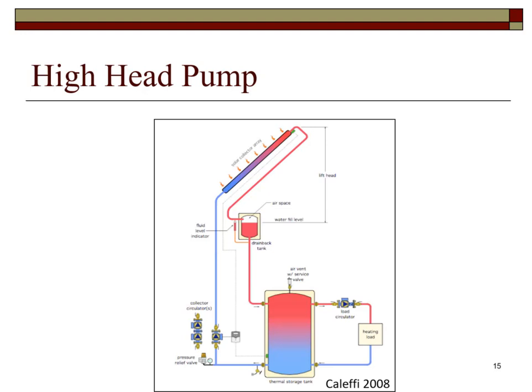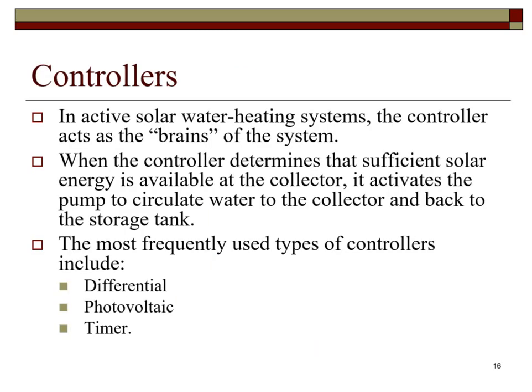Here is shown the drain back system. The pump is required to have high pressure capabilities at startup. The pump must push water to the top of the solar thermal collector during startup. After startup, the pump is only required to provide the standard pressure. There must be some method to control the pump.